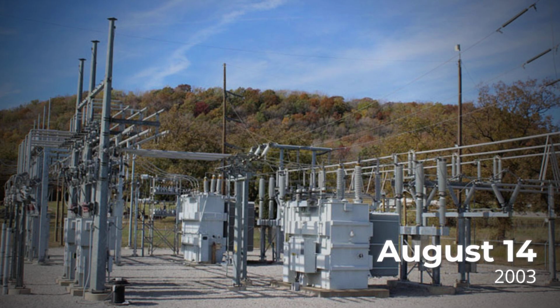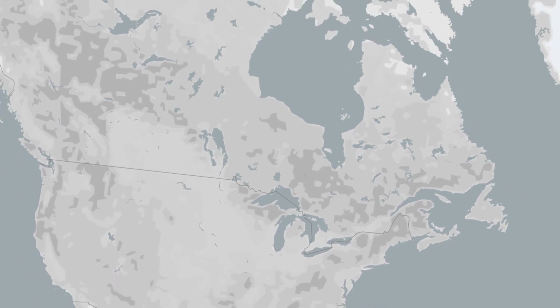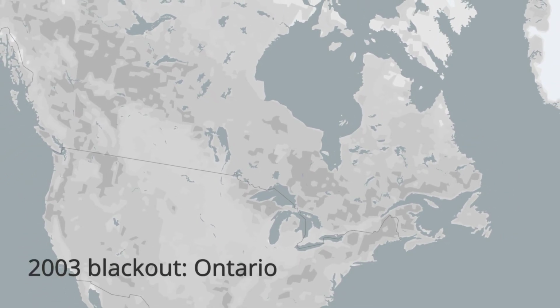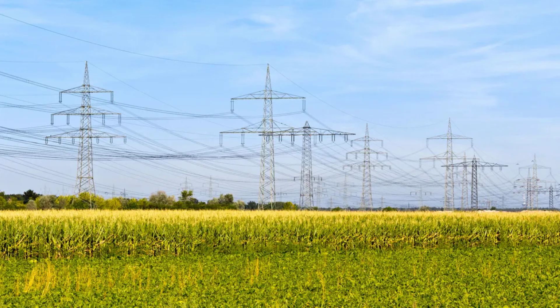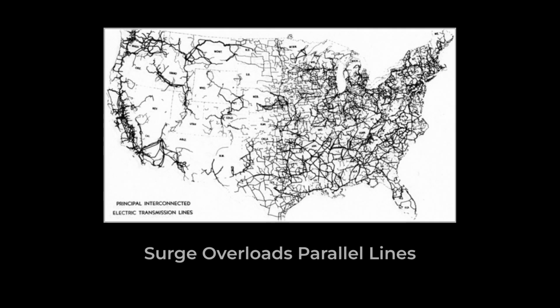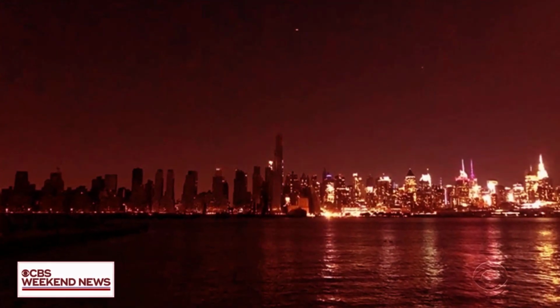On August 14, 2003, a single line fault in Ohio set off a sequence that blacked out large swaths of the northeastern United States and Canada. The initial loss of a 345 kilovolt transmission line forced power onto parallel corridors, overloading them within minutes. Protective relays tripped additional lines as currents exceeded thermal and voltage stability thresholds. In less than 2 hours, cascading failures darkened New York City, Detroit, Toronto, and hundreds of smaller cities. Over 50 million people lost power.